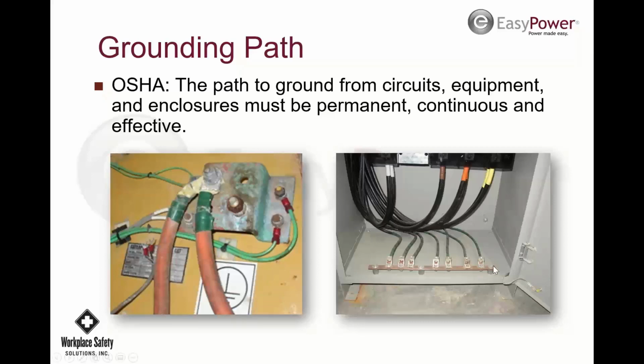So this is a grounding bus. This is a grounding bus, but it's a piece of channel. It's not really designed for electrical. But this is a good solid, low impedance grounding bus. We want less than 25 ohms of resistance on our grounding bus systems.